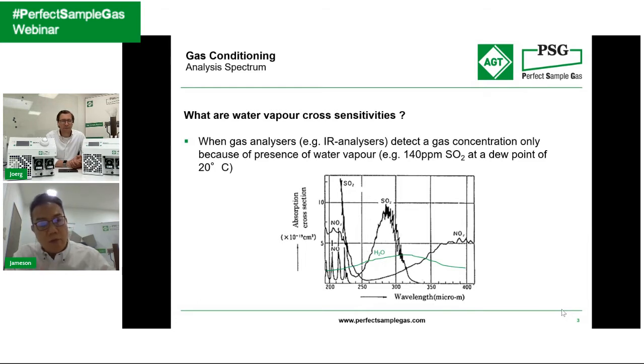There are also incidents where maintenance personnel notice the rotameter, the flow meter just before the gas analyzer, is pretty sticky. The ball, the indicator, sticks to the glass, and maintenance people have to create some light vibration to regulate the flow. But what is the reason for all this?